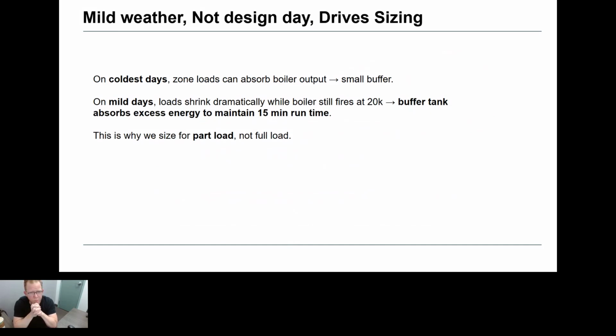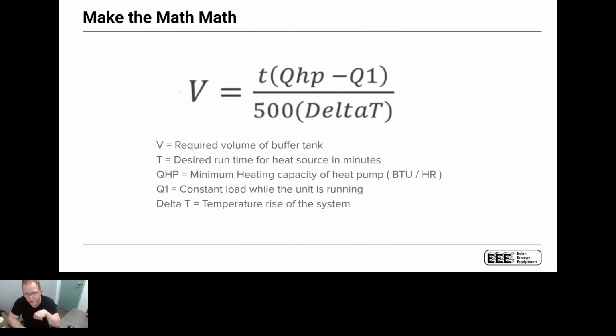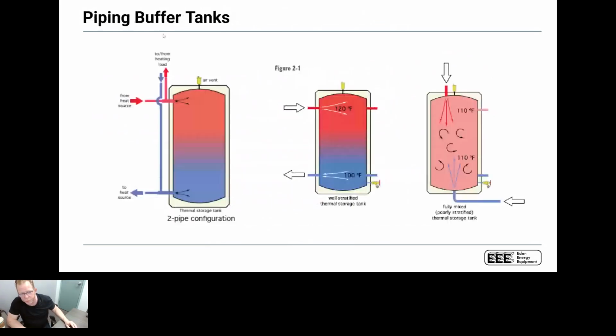But this is the really big one to keep in mind when it comes to buffer tanks: the buffer tank at design you may not need, right? If it's in the middle of February, my 5-ton heat pump probably doesn't need the buffer tank. And that's where this particular piping setup is slick. It's a standard two-pipe configuration, where when the heat pump is running, all of the heat that needs to go to the load is going to the load. Any of the heat not needed by the load is going into the tank. So I'm a huge fan of this setup.